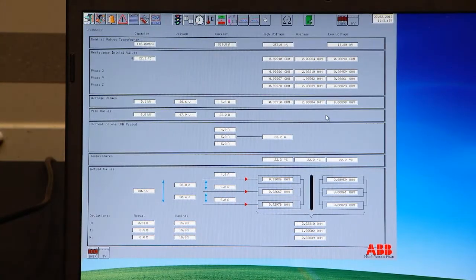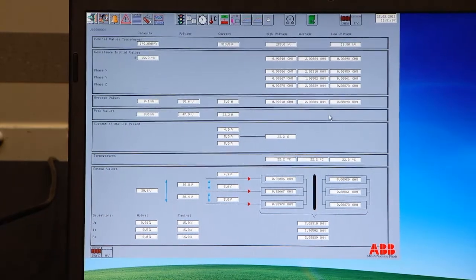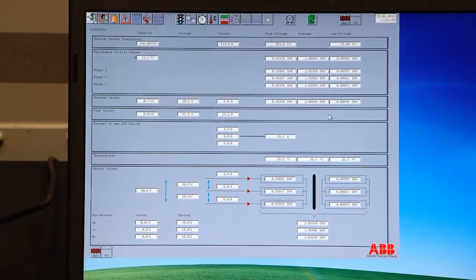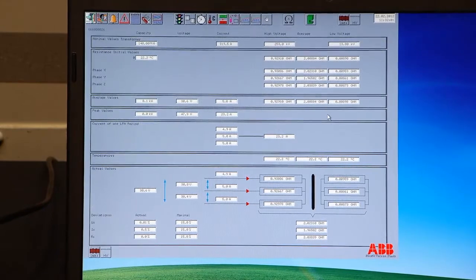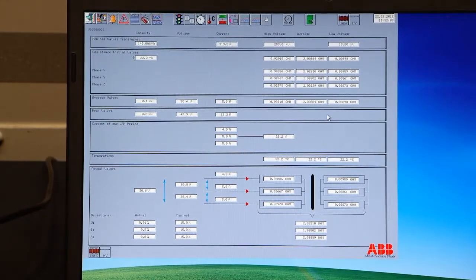But we are heating to a physical temperature, not relative. To an exact 110 degrees is our normal end temperature. And how that transformer is designed, since we are heating it at the end without any cooling. We don't have any oil or anything cooling the transformer. Yeah. So we are only concerned about the insulation temperature. Okay, initial resistance done.